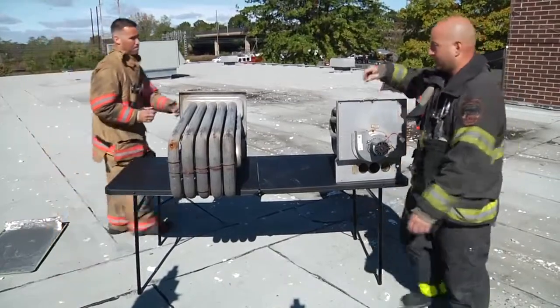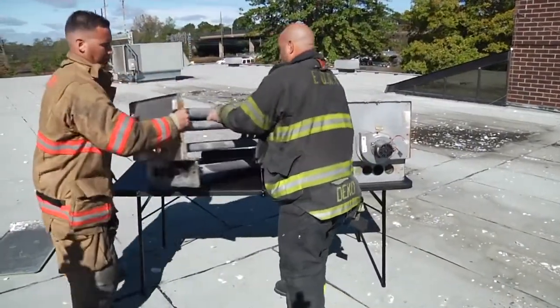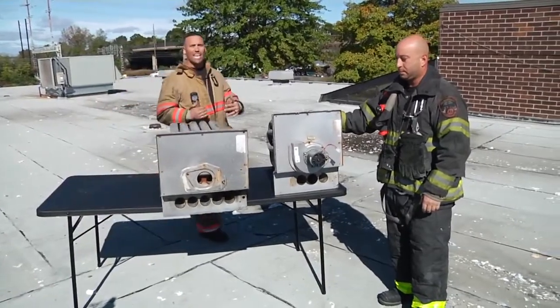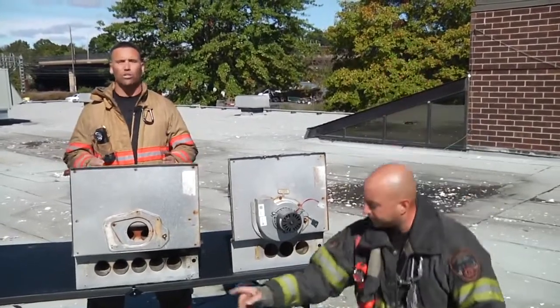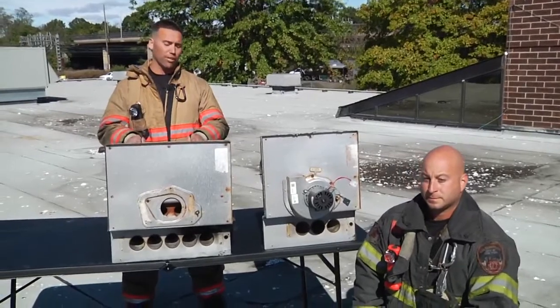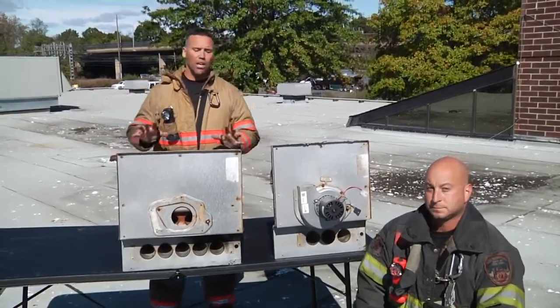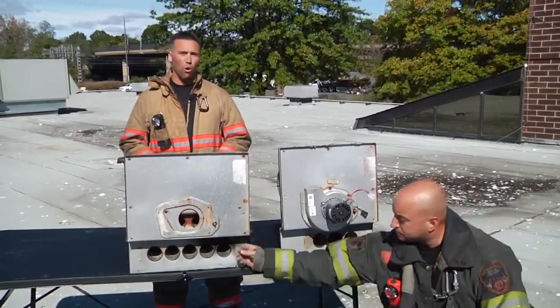Another emergency is something we refer to as flame rollback. Instead of the flames coming in nice and smoothly through these tubes and exiting out into the atmosphere, you can get actual differentiating pressures on the tubes and the outside ambient environment. When this happens, instead of the flames coming through smoothly, it's going to cause a negative pressure that's going to push the flames back and they're going to come out those holes there.